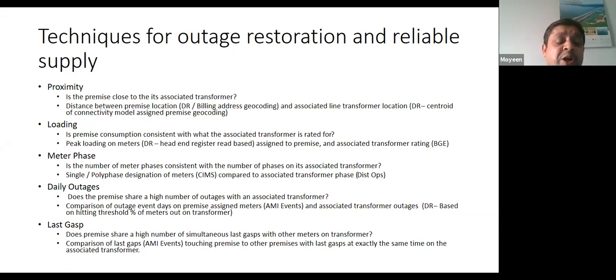I am talking about the use of a smart meter to check the health of the network, or to guide our operations team, whether these assets are good enough to carry forward, or whether we can add load to it, whether we can further leverage the existing network. Suppose it can serve 200 consumers, but by doing proper phasing and proper loading, 20 to 30% more consumers can be added. So they are saving on not having to augment their network. They are able to optimize the existing network, which is a real benefit in terms of not needing to augment the network, as well as maintaining the health of the network and equipment.